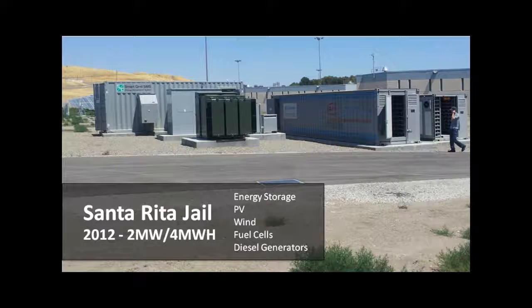This is a pretty famous microgrid completed back in 2012. It was backboned by a 2-megawatt, 4-megawatt-hour energy storage system, with 3 megawatts of PV, some small wind, a 1-megawatt fuel cell, and several diesel generators. In the past, when there was an outage at the utility, the jail would go dark for about 10 seconds, a long time if you happen to be a guard. So they received funding to put in this microgrid, and now they have continuity of power throughout the day, and are also able to reduce their utility bill through demand charge reduction and shifting peak to off-peak.